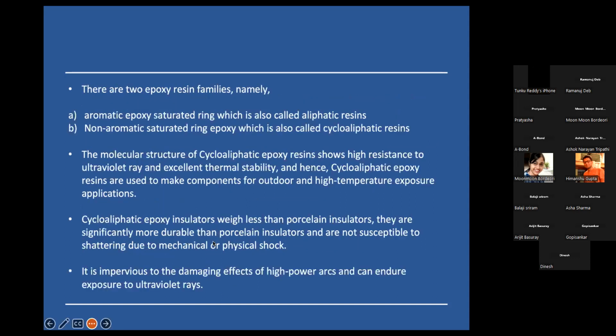Now when it comes to epoxy resin families, the main two are aliphatic resins and cycloaliphatic resins. When it comes to cycloaliphatic resins, we have noticed that in manufacturing applications, they're more useful for outdoor applications and high temperature applications. This is because they have a particular molecular structure which has higher resistance to UV rays and excellent thermal stability. Another advantage of cycloaliphatic epoxy insulators is that they weigh less than porcelain insulators and are much more durable. They can easily withstand high power arcs, mechanical shock, and also ultraviolet rays.